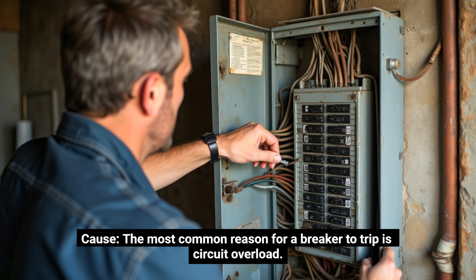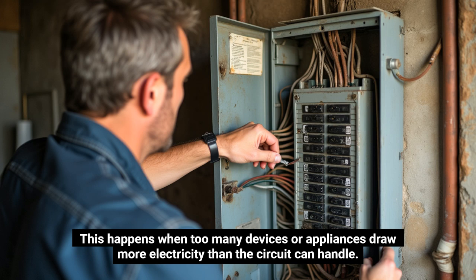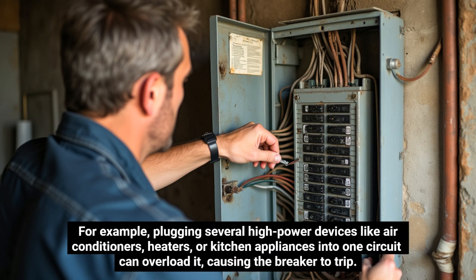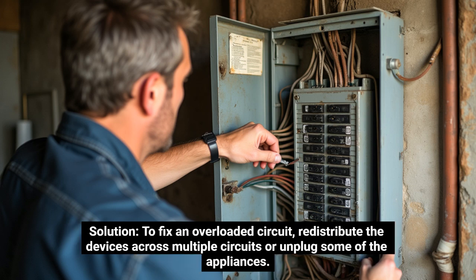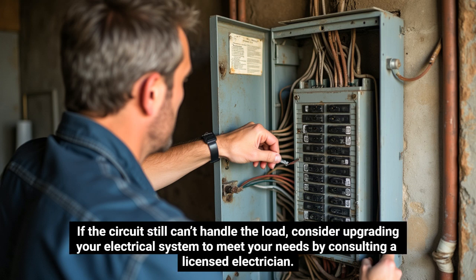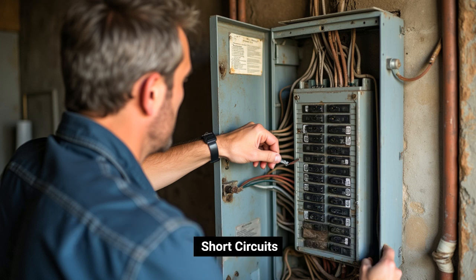Cause: the most common reason for a breaker to trip is circuit overload. This happens when too many devices or appliances draw more electricity than the circuit can handle. For example, plugging several high-power devices like air conditioners, heaters, or kitchen appliances into one circuit can overload it, causing the breaker to trip. Solution: to fix an overloaded circuit, redistribute the devices across multiple circuits or unplug some of the appliances. If the circuit still can't handle the load, consider upgrading your electrical system to meet your needs by consulting a licensed electrician. Short circuits.